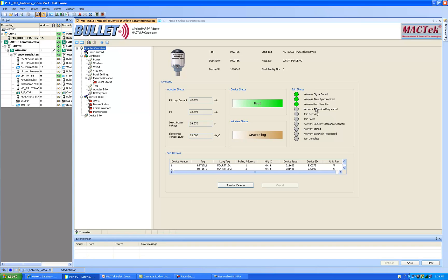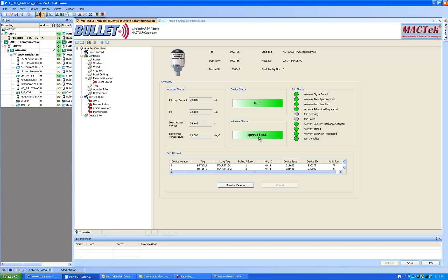The next step it will be requesting network admission. Now our status is switched to the joining mode. Network admission has been requested. Now we have security clearance and it goes pretty quickly here. The network has been joined. Now it's requesting its bandwidth to get its time slots when it communicates and there it is. Now that we have a complete join our field switched to green here it shows operational and our bullet should be connected to the gateway.